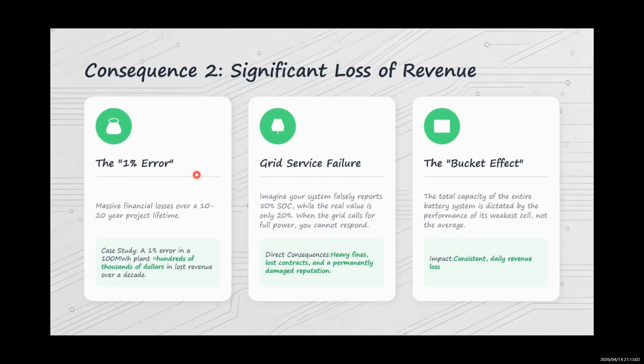Next, let's talk about money. Just imagine a 1% error in SOC estimation. It might sound trivial, but for a 100 megawatt-hour system, it means losing millions of kilowatt-hours of energy over 10 years and hundreds of thousands of dollars in losses. Even worse, imagine failing a grid service because your SOC display was wrong. You think you have 50% SOC, but you really have 20% SOC. So you cannot deliver enough energy when needed, leading to a penalty or loss of qualification from TSO or DSO.